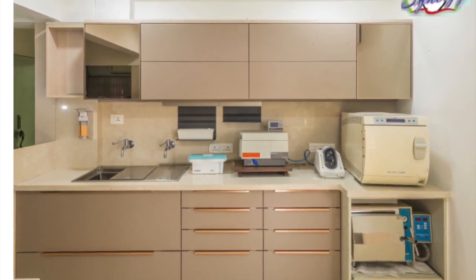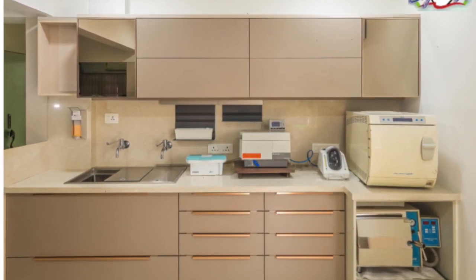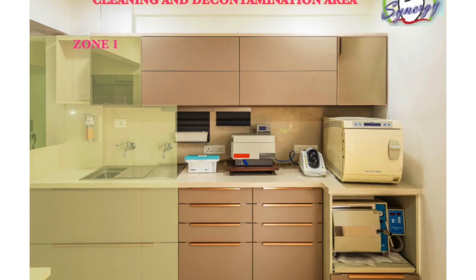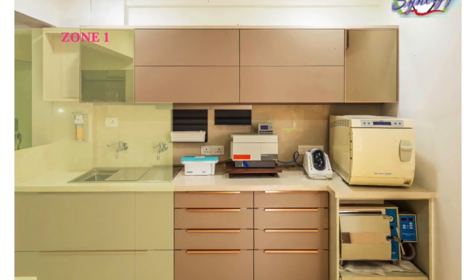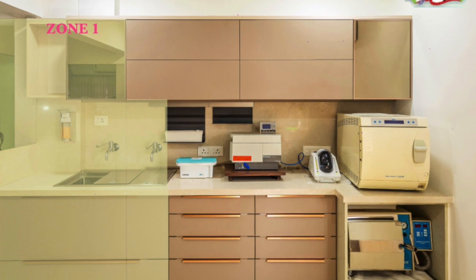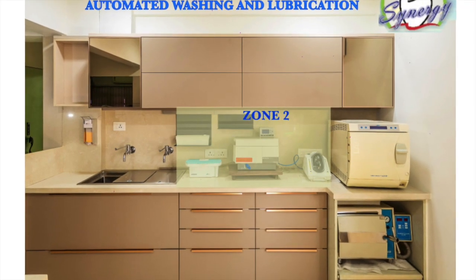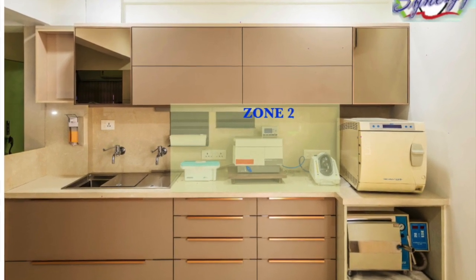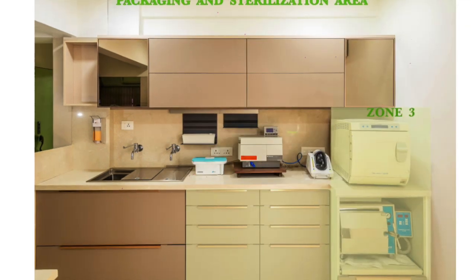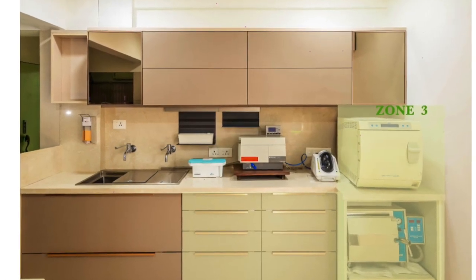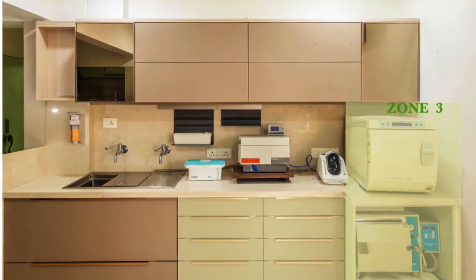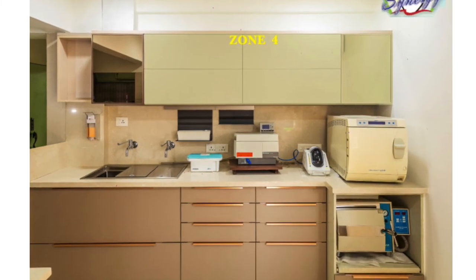We have a contemporary design with 4 critical areas. Zone 1, which is the cleaning and decontamination area. Zone 2, which is the automated washing, rinsing, drying, and lubrication area. Zone 3, which is the packaging and sterilization area. And Zone 4, which is the storage area.